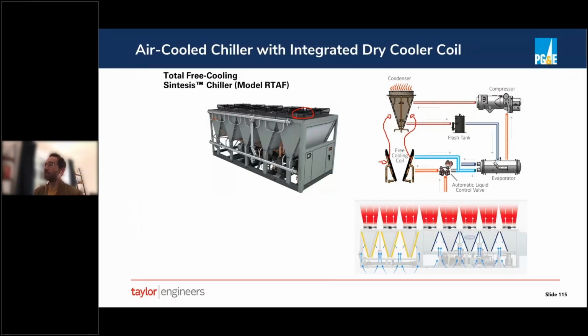One potential downside with this system design, however, is that because we're using the same set of fans, this set of fans has to do two things. One, it's trying to provide as much free cooling as possible, but it also needs to maintain efficient head pressure in the refrigeration circuit. Head pressure is effectively the difference between the saturated condensing pressure on the condenser side of things and the saturated suction temperature on the evaporator side of things. Most chiller systems, particularly those that use oil, need a minimum amount of pressure differential in order to properly operate.